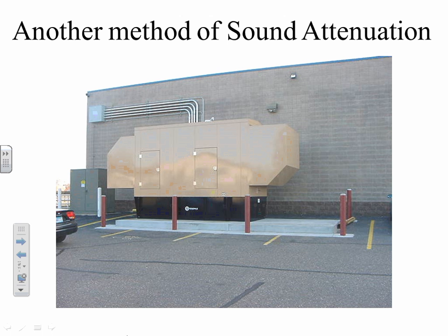Here's another method of sound attenuation. This one is a very clean design. Again, no louvers on it or anything. So we've got an inlet and an outlet. And you can tell the inlet always because it's coming in from underneath. This is open. So it's sucking direct down over the engine, out and up. So a larger version of the inlet and the outlet. This time we're attenuating the inlet this way.